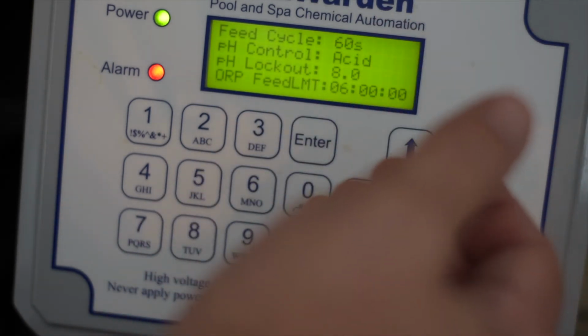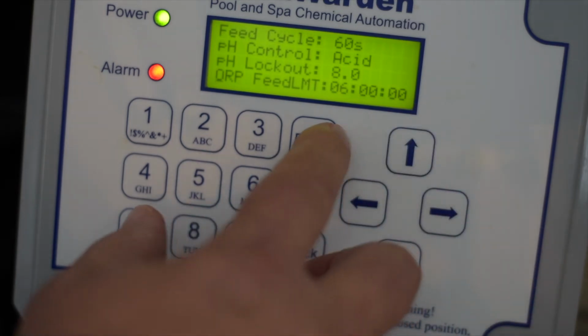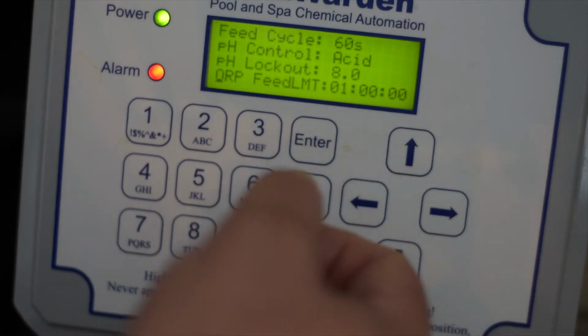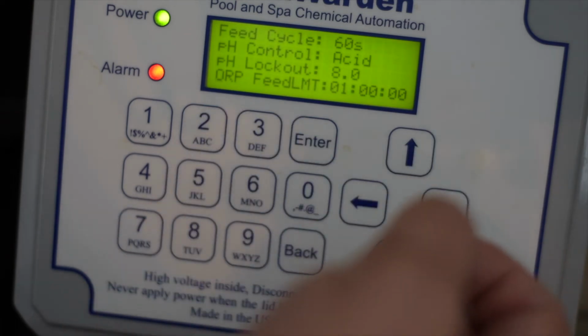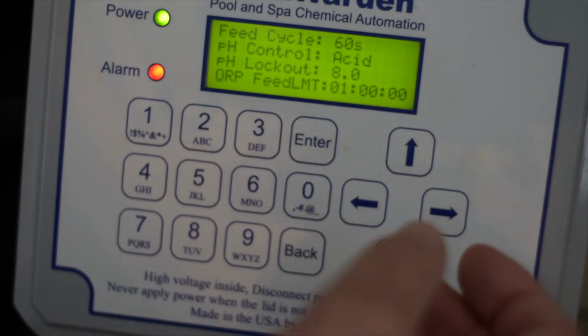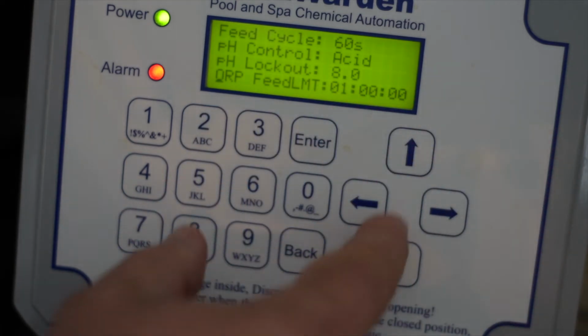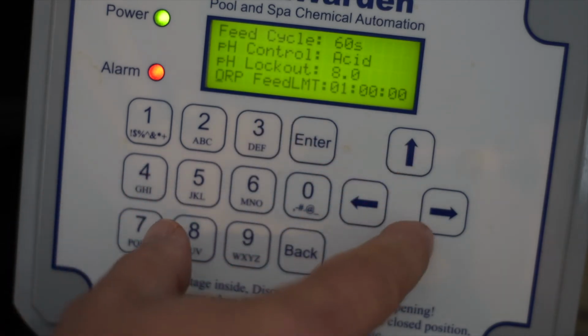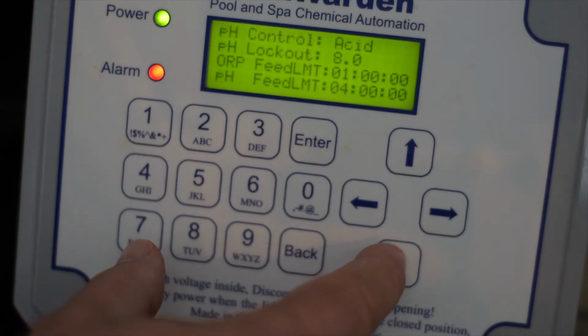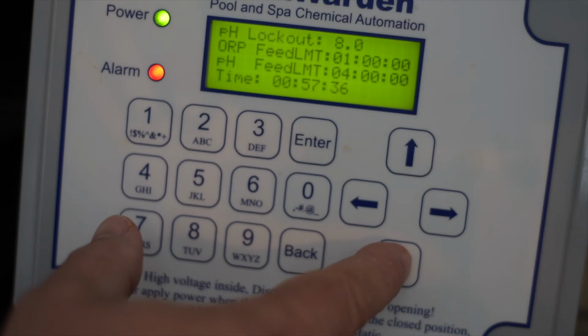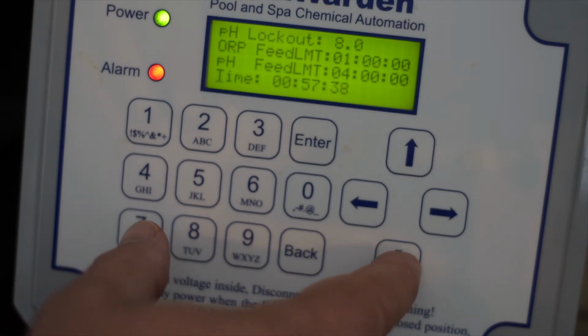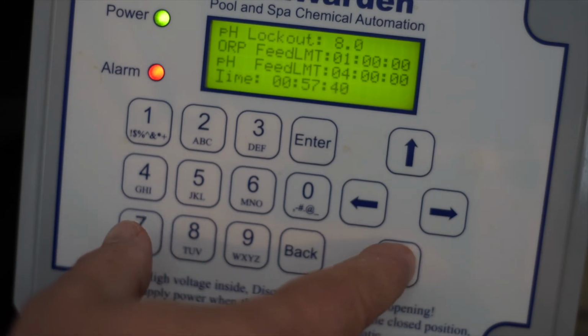If it starts, say, at 9 o'clock, and we had that at 1 hour, then at 10:01, if it hadn't reached its set point, it would lock out. Again, you can go from 1 to 6 hours. Same thing on pH, which, from 1 to 6 hours, is plenty of time for any properly sized pump to correct the problem.